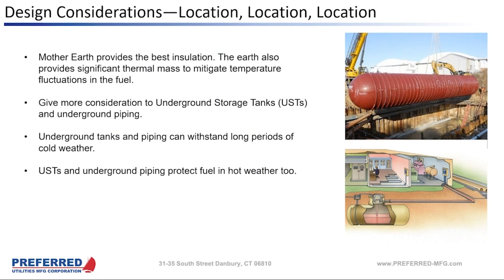So the first thing to consider if you have a new system is the location of your tanks and your piping. If you can do underground tanks, the earth is not only going to insulate them, but there's also a lot of thermal mass in all that earth that takes a long time to cool down. So underground tanks and underground piping have their own insulation, and a lot more thermal mass that resists being cooled off with intermittent cold weather.